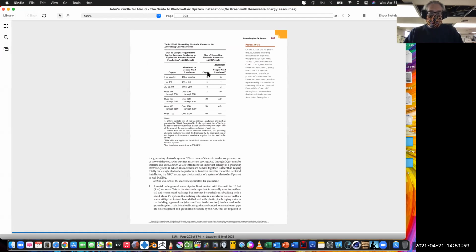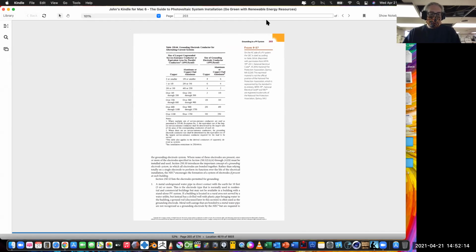And then follow this chart on how big of an electrode you need. So if we're doing 1/0 wire, we're going to have to get a bigger grounding electrode. And if we're not buying copper, we're buying copper clad aluminum, we're going to have to get a different size too.